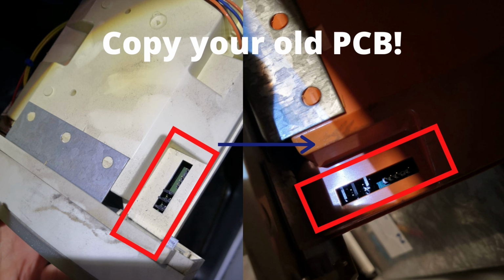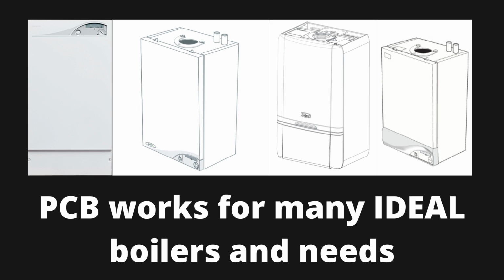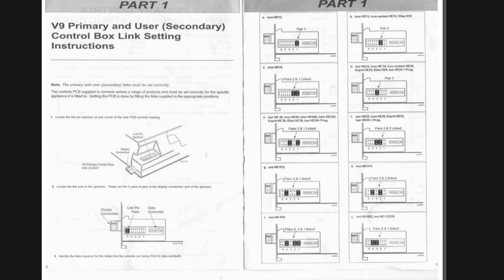These essentially short these two headers, and you have three of them in my case. And these need to be put into a certain combination, because this PCB is actually a controller that can be used on any boiler that Ideal makes. A lot of their boilers use this PCB, and if you put these in different patterns, then it tells the controller which boiler you are using. So for an example, here is the manual that shows the different combinations and what combinations are for what boilers.